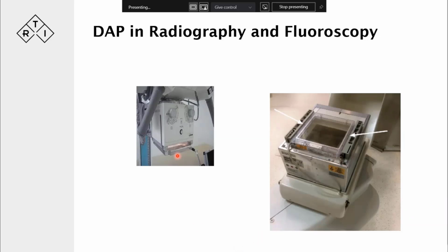Of course, these then would have a calibration of transmitted air kerma, so they keep track of what comes out of the complete collimator package, of which the DAP chamber is a part. So they would have a calibration corresponding to the transmitted, whatever comes out of the DAP chamber. That's what it's measuring: the dose, the DAP value that reaches the patient.